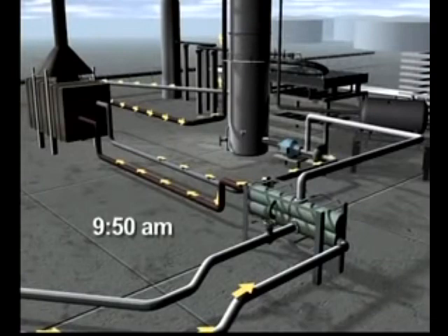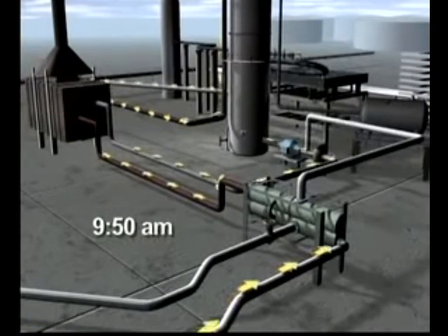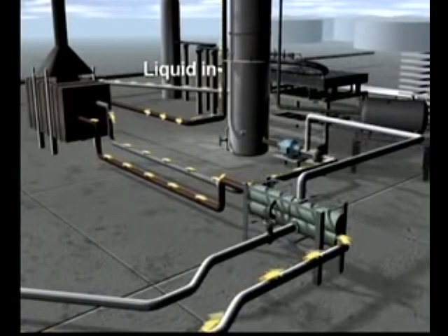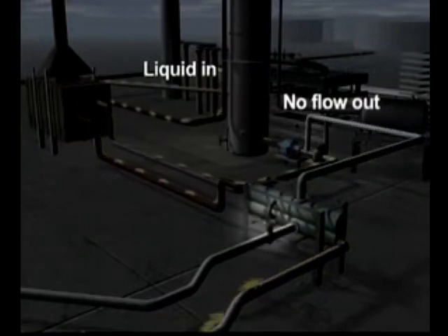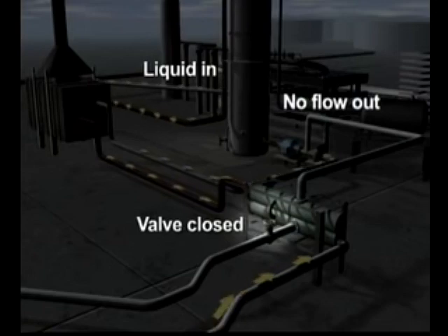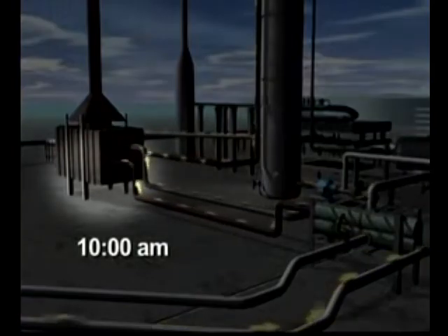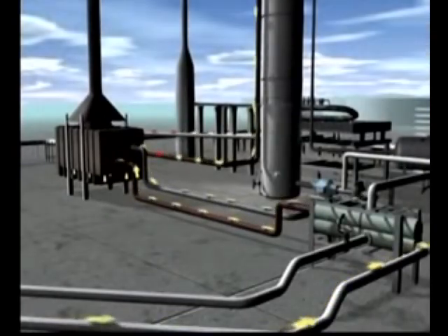At about 9:50 a.m., operators began circulating the liquid feed and adding more liquid to the already full tower. Even though the liquid was going into the tower, there was no flow out contrary to the startup procedures — the valve that controlled the liquid flow out of the tower was left closed. Ten minutes later, at about 10 a.m., operators lit burners on the furnace to begin heating up the feed, part of the normal process.